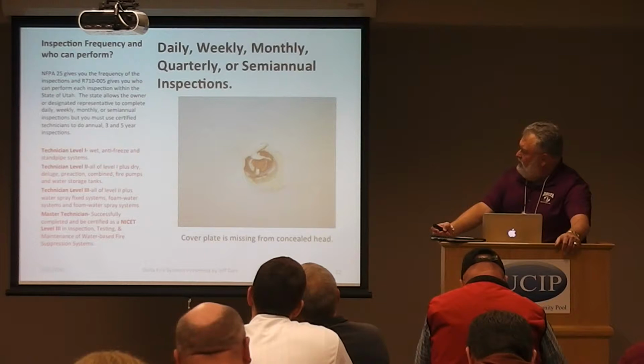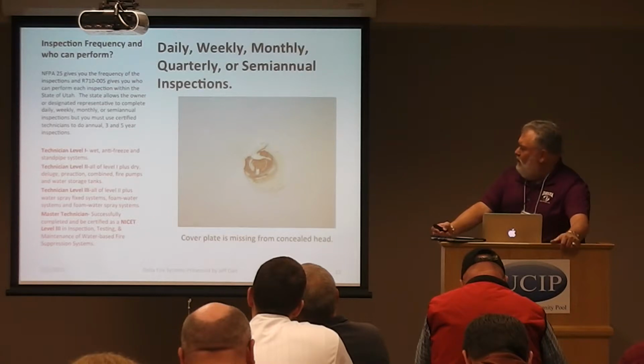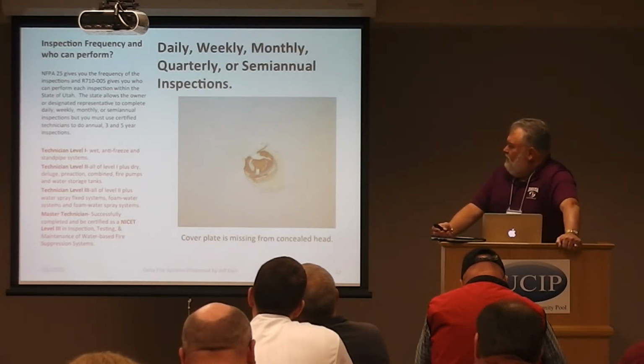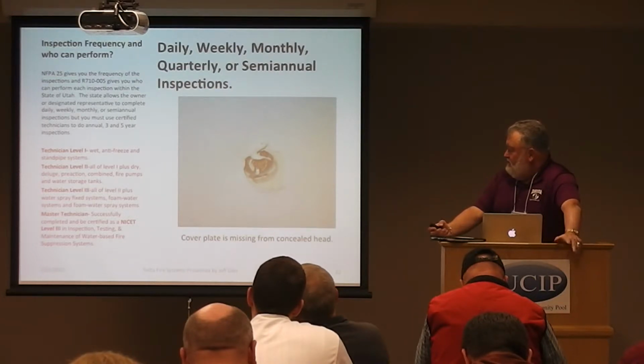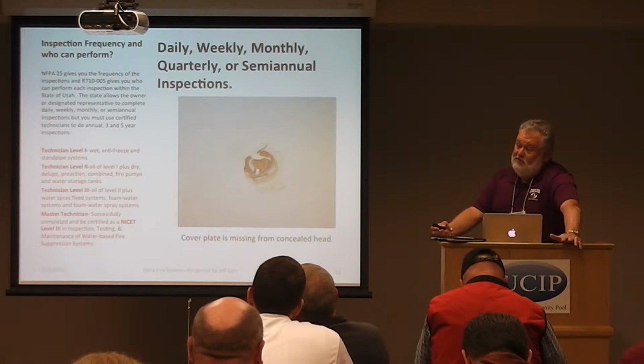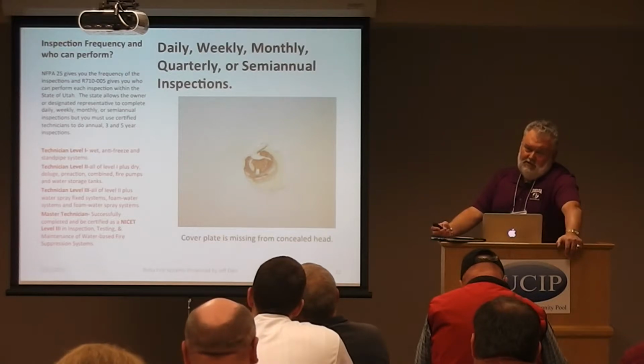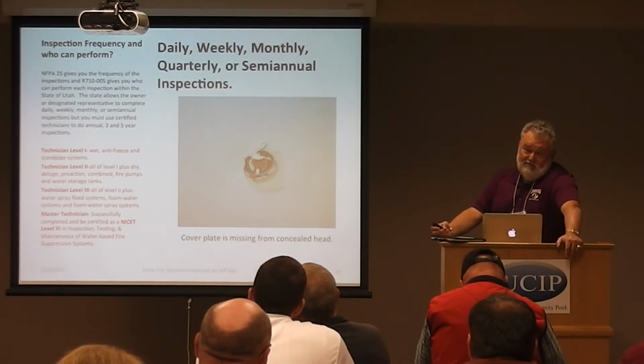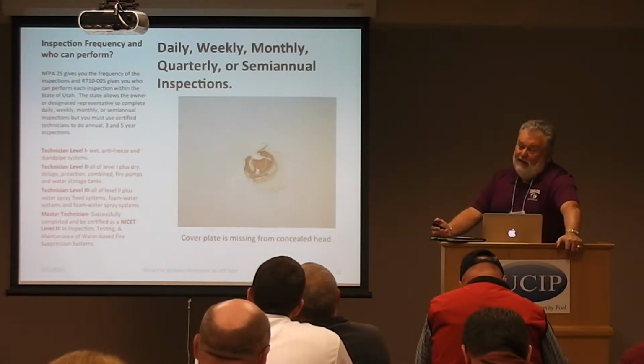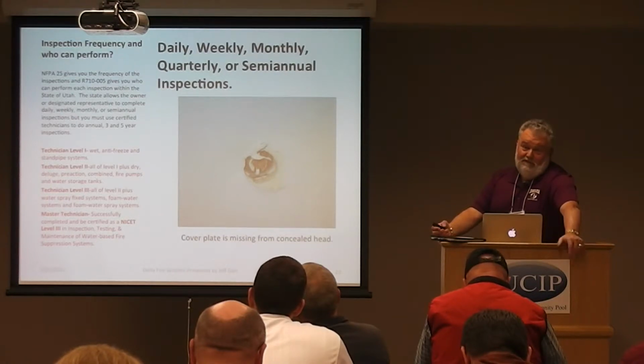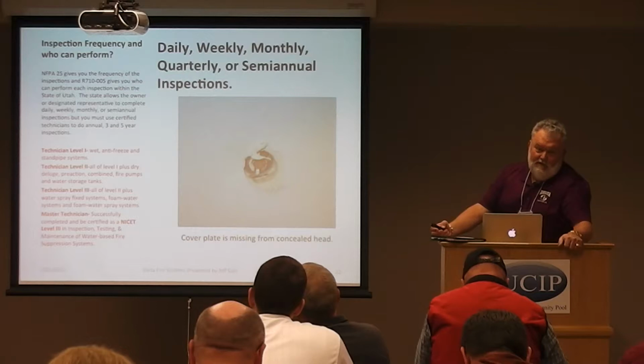If you go to a Tech Level 2, that guy has to pass everything as far as the Tech Level 1, plus take that written test on dry, deluge, pre-action, combined systems, fire pumps, and water tanks. And Level 3, he has to pass everything for Level 1 and 2, plus he has to do the written test on water spray systems and foam water systems. Those are specialized systems. You'll see them in power plants, you'll see them at refineries, aircraft hangars have foam systems. They definitely want people knowledgeable on those types of systems, because if you dump a high expansion foam system by accident, you're talking hundreds of thousands of dollars there, plus the potential for damage of any aircraft and so forth. So they want to make sure that you know what you're doing.